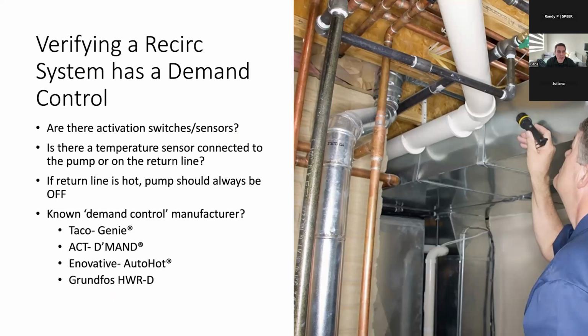Verifying if a recirculation system has a demand control. Okay, so let's say you're an inspector and you want to know, well, is this pump an on-demand system? So the first thing you want to know is, is there a temperature sensor connected to the return line? And if so, if my return line is hot, then that pump should be off. Anytime the return line is hot, that pump should not be running. And is it a known manufacturer of on-demand systems?